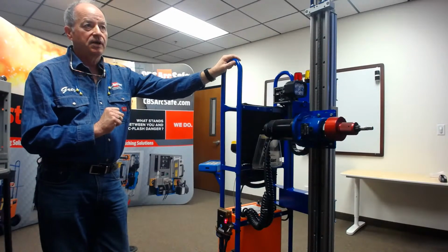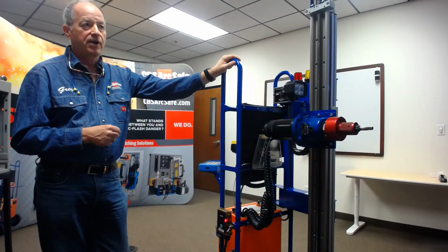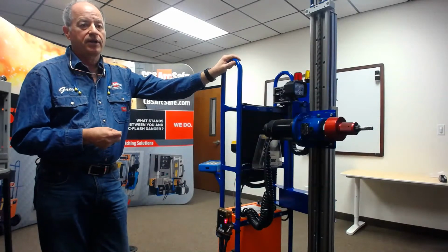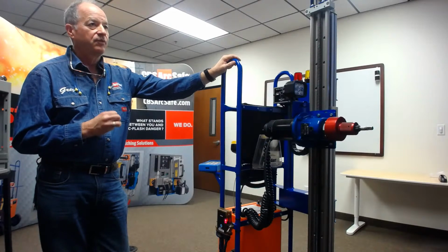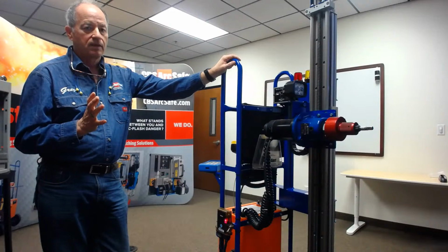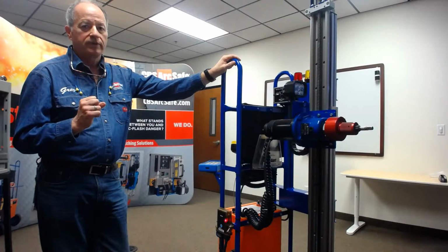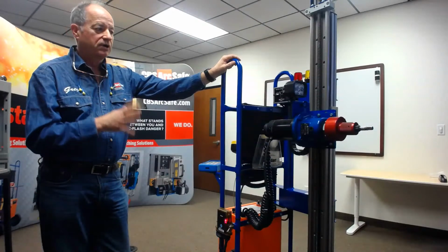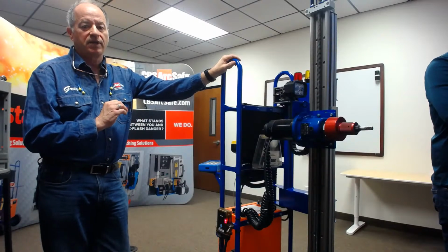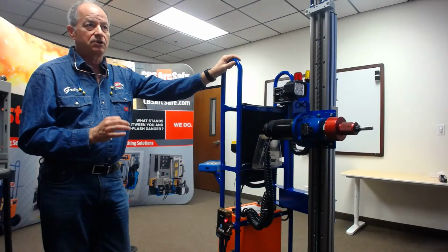And yes, we do have solutions for breakers with interlocks. We'd like to know which type you've got. We've dealt a lot with the ABB HKs. We've got the NTs, the AdVac. We've got some Toshiba breakers we've dealt with. We've got the AMH breakers for GE. There's several out there that we've evaluated and done. Talking to RS2 stuff as well, the RS2 is for breakers that operators affectionately call using a dead man or suicide ratchet to get them in and get them out. And there's plenty of those that we've done. For the RS1, we've evaluated over 140 applications around the world for customers.